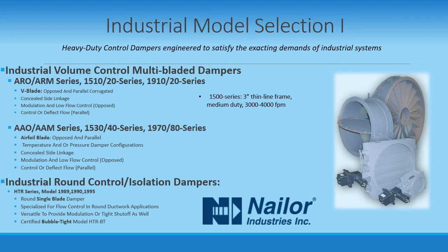Each series of damper comes in either V-blade or airfoil blade, with blade action both parallel and opposed. Parallel-bladed dampers have their blades oriented to open and close at the same time, same angle, and same direction, and are generally used for full-open or full-closed operation with the best control of airflow near their fully closed or fully open positions. Common applications of parallel-bladed dampers are gas turbines, scrubbers, fan inlets, and oxidizers, where on-off operation is at a premium.